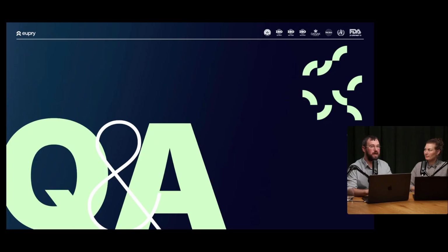Ongoing verifications are really good at catching, between calibrations, whether your equipment has experienced some type of failure or whether it has drifted outside of requirements. So let's say during an ongoing verification, you'll see that, well, this seems to have drifted. Let's do a calibration. Maybe that's a whole other point for a different webinar. But there are many rabbit holes. Yeah, there are.